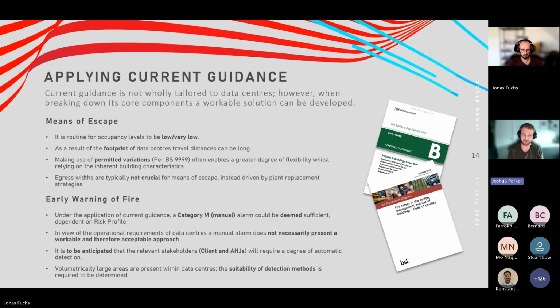But typically, if it's A2 or A1, then category M would be acceptable, but really it isn't acceptable because of the number of systems that need to interface with the fire alarm throughout these buildings. In view of the operational requirements of data centers, they just don't work. There are a number of systems, such as VESDA, for example, that is often a client requirement because of high ceilings. It just wouldn't work through the adoption of a category M alarm. So providing a suitable base alarm provision that further systems can tie into is an important consideration.